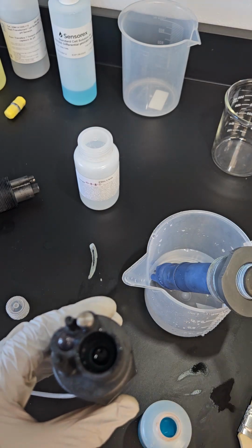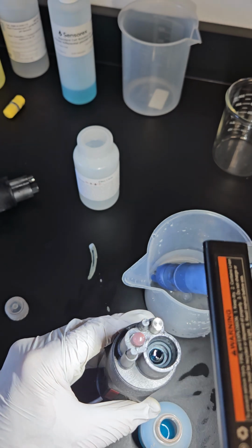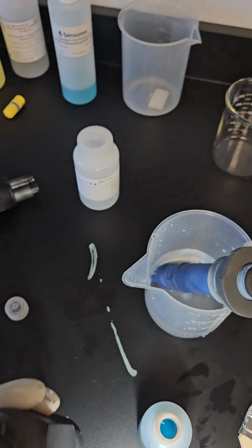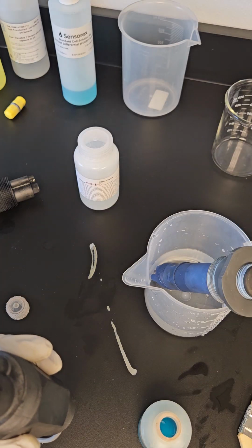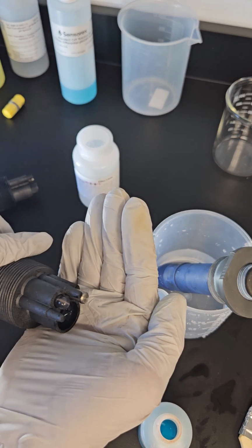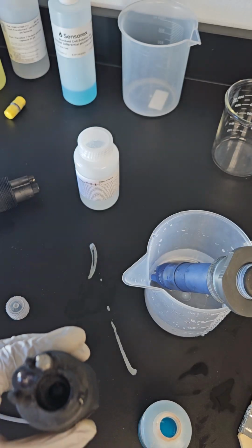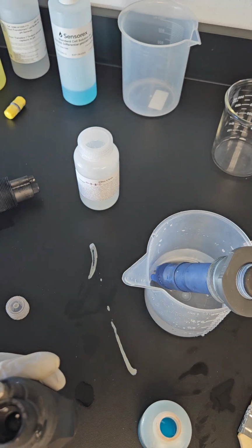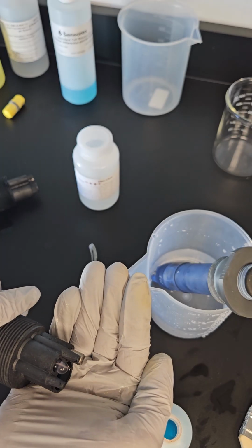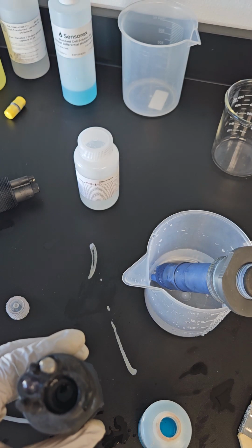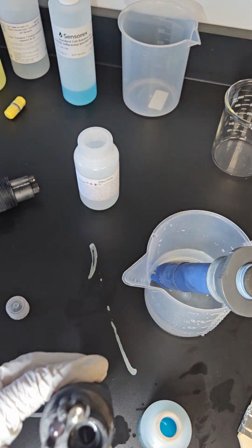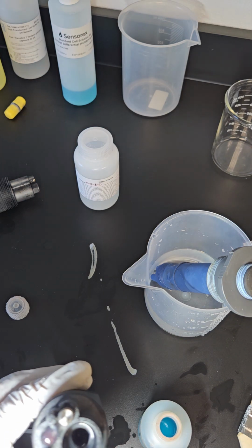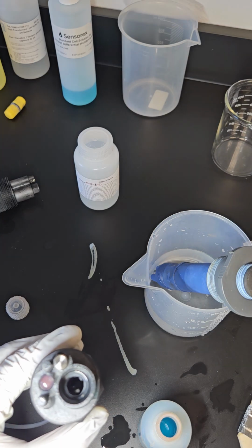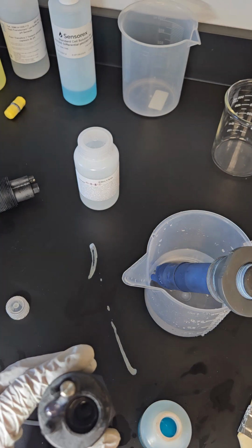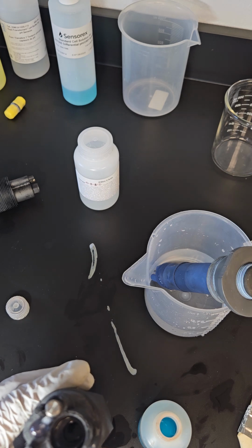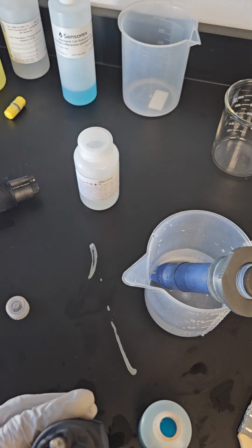So here it's probably a little bit high. You've got to look at it and get it on the bottom 1 or 2 threads there, so you can pour out a little bit, get it to the point where it's just covering the bottom 1 or 2 threads in the bottom of this cavity. Otherwise it's going to over pressurize itself when you put the salt bridge in. Okay, there it is. Now it's down there at the bottom of the threads. You can't have a cavity though, so it has to actually be into the threads and not leaving a void just below the threads, where the roof of that cavity starts to go to the side. It can't have air there, so it has to be into the actual threads themselves.